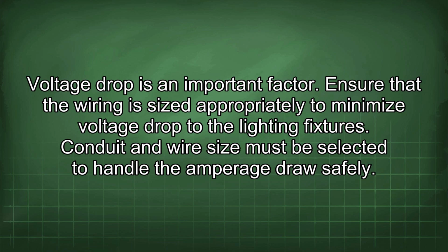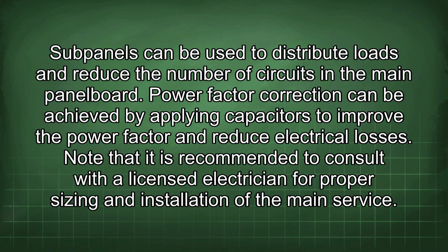Voltage drop is an important factor. Ensure that the wiring is sized appropriately to minimize voltage drop to the lighting fixtures. Conduit and wire size must be selected to handle the amperage draw safely. Subpanels can be used to distribute loads and reduce the number of circuits in the main panel board. Power factor correction can be achieved by applying capacitors to improve the power factor and reduce electrical losses. Note that it is recommended to consult with a licensed electrician for proper sizing and installation of the main service.